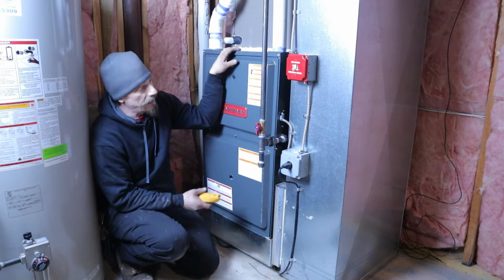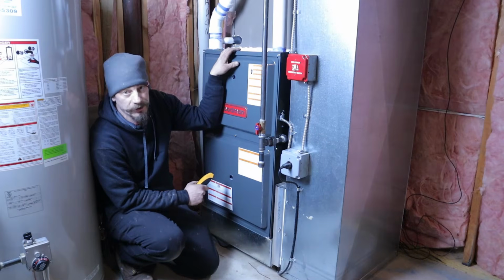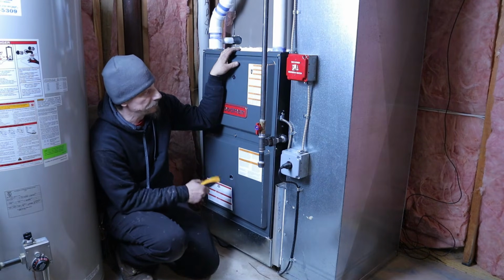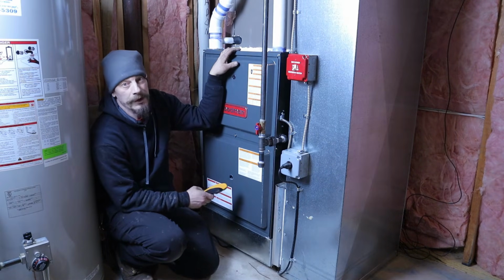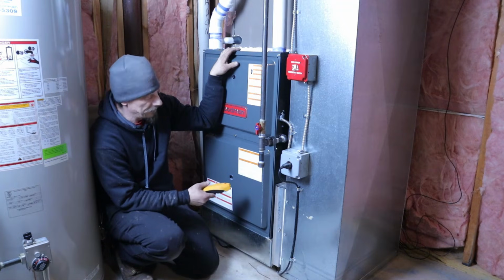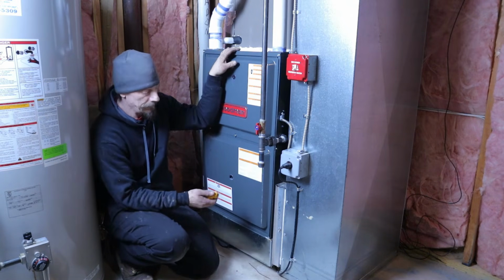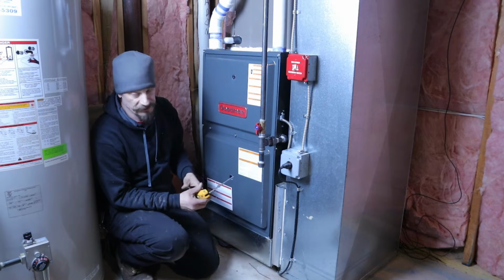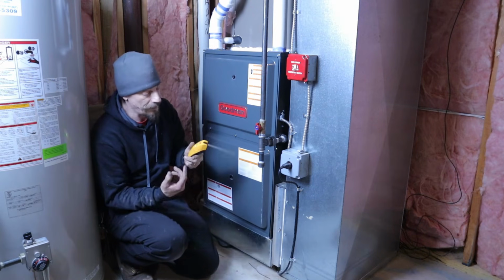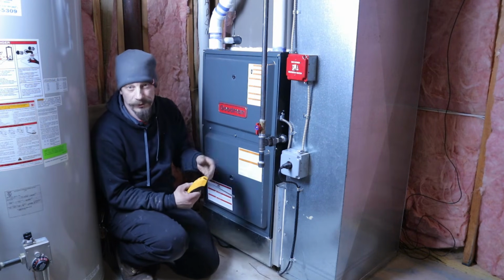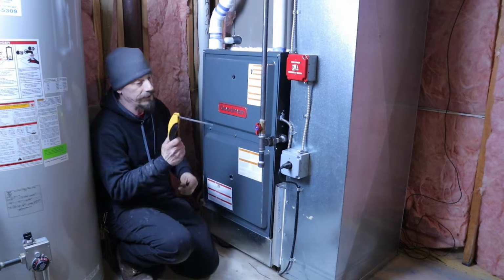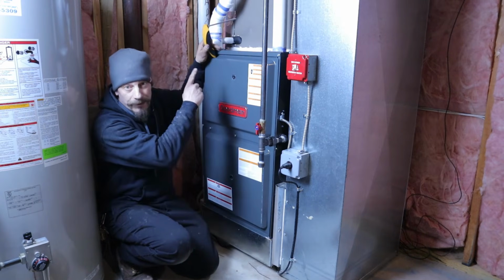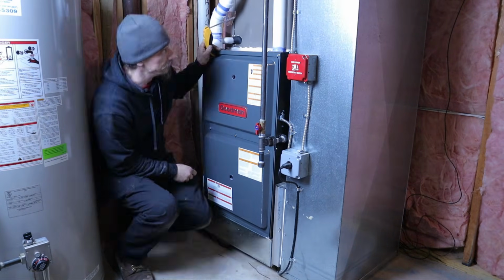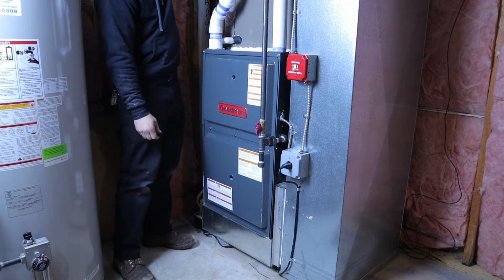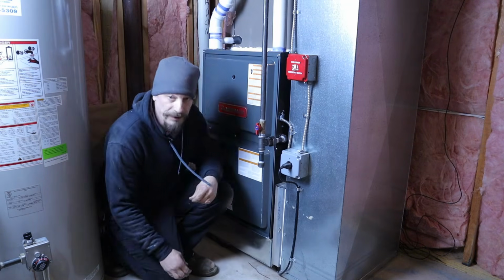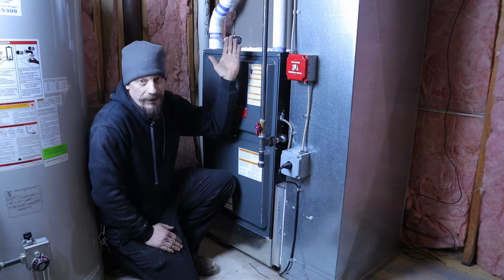So what we're going to do now is I have Juan going upstairs. He's going to turn the breaker back on, and he's going to set the thermostat to call for heat, and I'm going to do what's called a temperature rise test. So basically what I'm doing, I'm going to take my probes. I have UEI probes here. They're wireless, but you can do this with a regular thermometer. So I'm just going to take one probe, and I'm going to put it up in the ductwork above the furnace. And that's going to take my temperature of the heat coming out of the furnace.